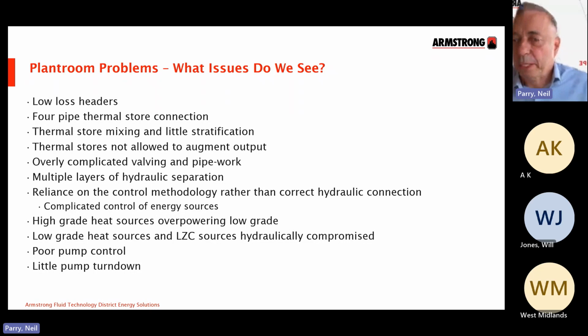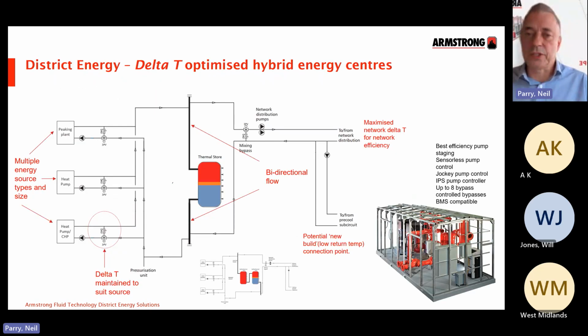Now, this schematic here, I'm going to speed up a little bit. This is a schematic that's shown in the design guide for CP1 that was released a year and a half ago, a couple of years ago. What it basically is showing is your thermal store here in the heart of the energy center, connected by 2 pipes, which are bidirectional. And it's really important to point out here that what is not happening is a circulation of flow down through the store and back to the energy sources. This pipe work here is bidirectional, and what we're doing is holding a nice stratified layer between the hot and the cooler water, and because it's stratified, we can measure its location point within that thermal store and also its direction of travel.